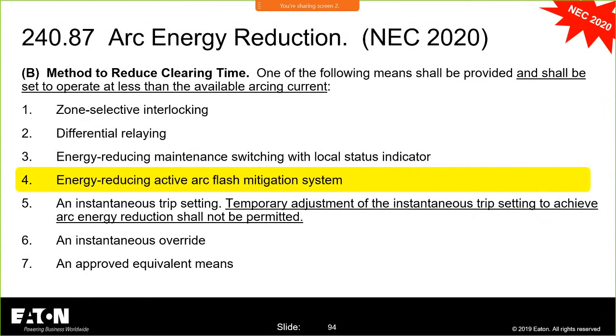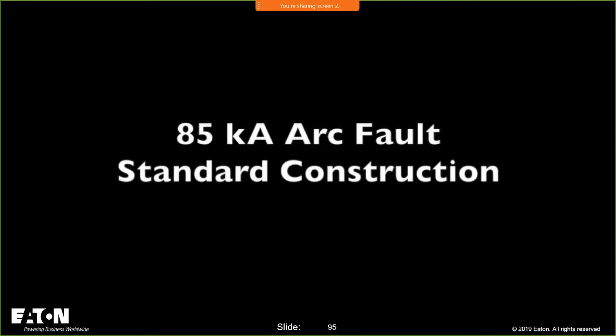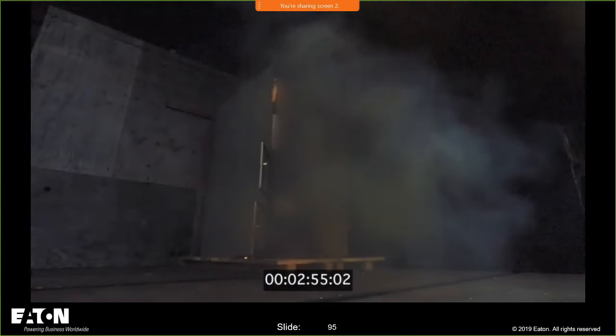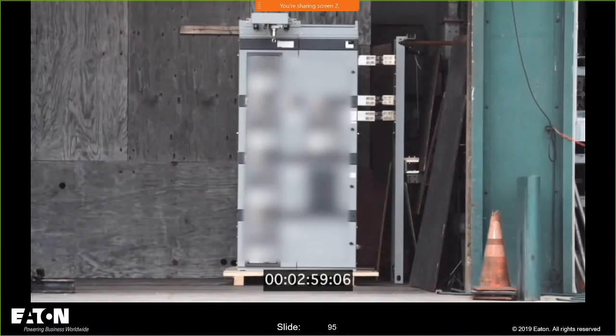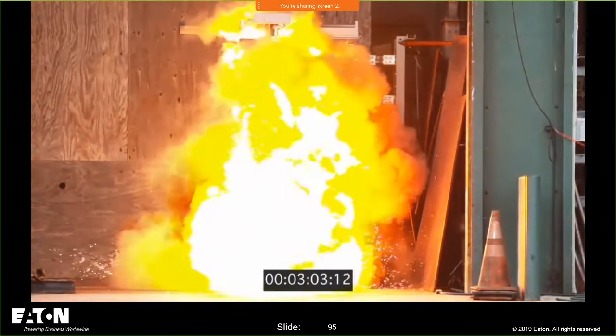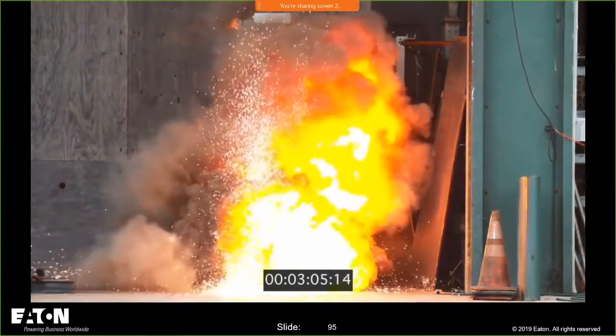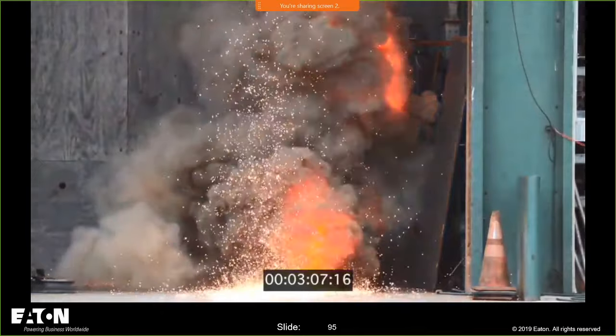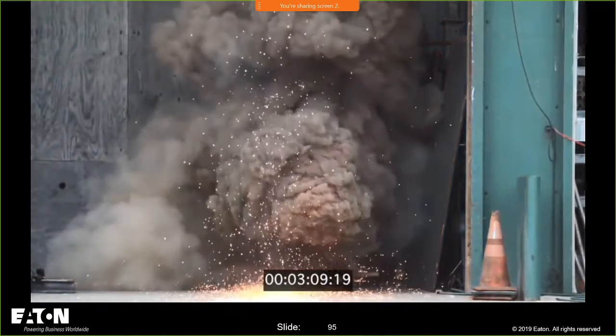Now, the active arc flash mitigation system. Got a treat for you. 85,000 amp arcing fault. That is humongous. You don't want to be in front of that. 85,000 amps. We're showing that will just rip through equipment. It'll take months to repair this application.